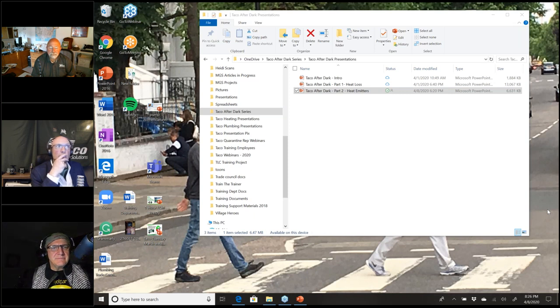Go ahead, Dave. I'm all about putting this thing on outdoor reset. Get that boiler on outdoor reset with a DHW priority control, which is going to take that boiler and bring it back up to a higher temperature. So take advantage of getting an external reset controller and modulate the water temperature. I mean, yeah, the boiler is going to be too big. We do need the size for DHW loads nowadays. And so that becomes an issue, definitely.